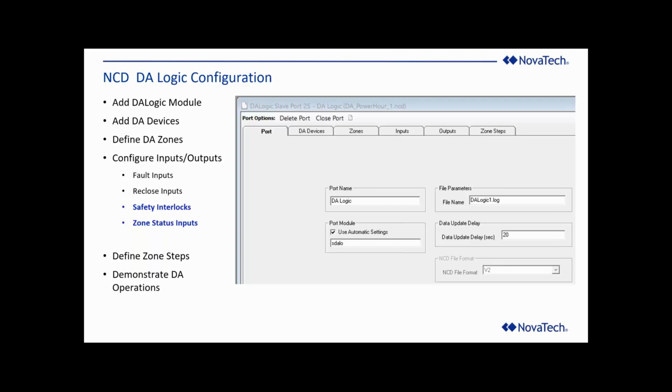That is a file that is stored in the Orion, and you can download it from the Orion to analyze after the fact. It will continue forever, actually. When it gets full, it will overwrite the existing file and create a new file. So it does not have a history forever. It simply fills up, and then it creates the last one. So after a DA event, you can pull that out of the Orion and analyze the system.